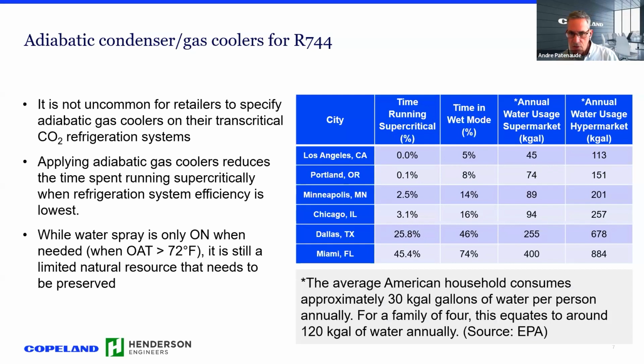In Los Angeles, you can see a runtime in supercritical is 0%, because anytime it is over 72 degrees, which is 5% of the time in wet mode, that's really the wet mode keeps it from going transcritical. And you see all the hours of operation and the percentage of transcritical runtime. And to the far right, you see the amount of thousands of gallons per year. So Los Angeles, for example, in a supermarket, 45,000 gallons in a year of water use for 5% of the year. Whereas Miami on a supermarket, it's 400,000 gallons a year.